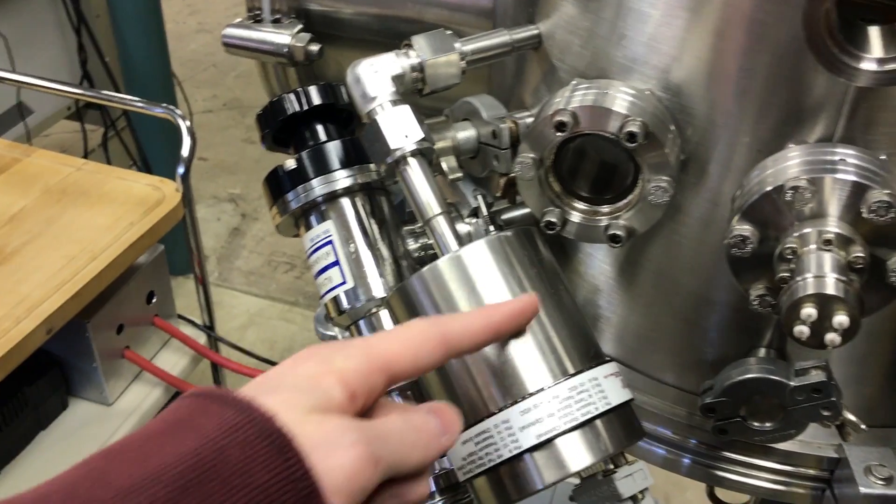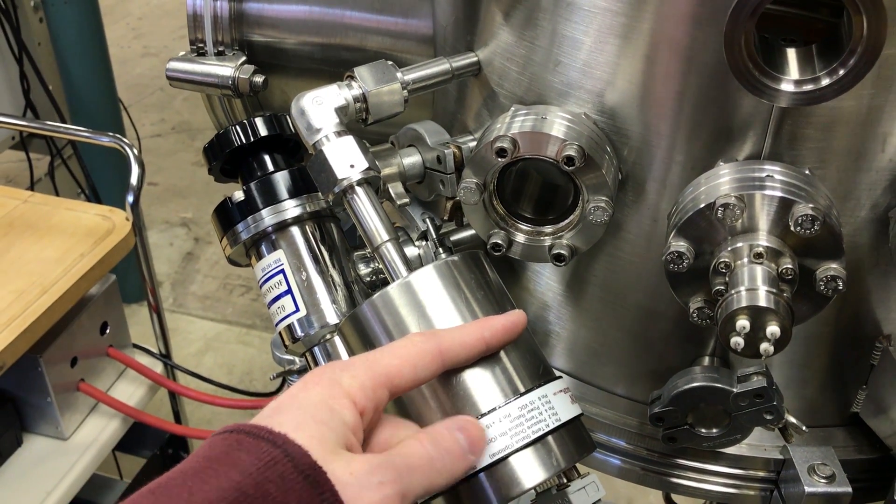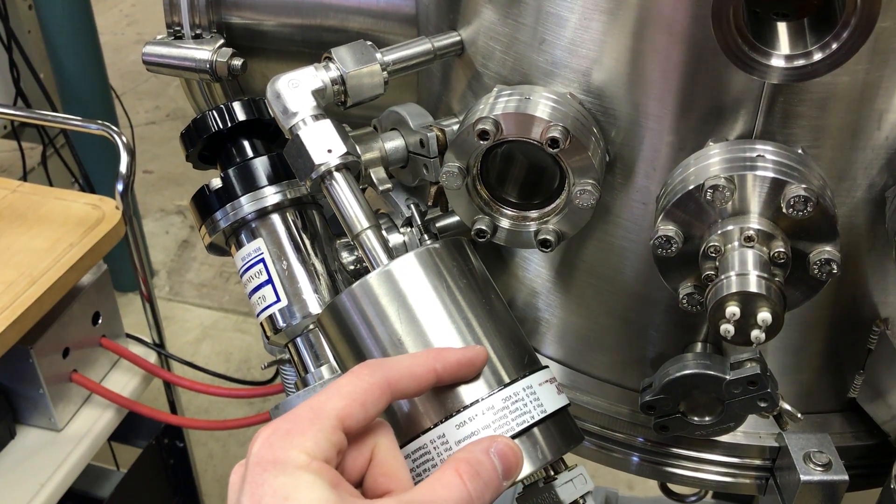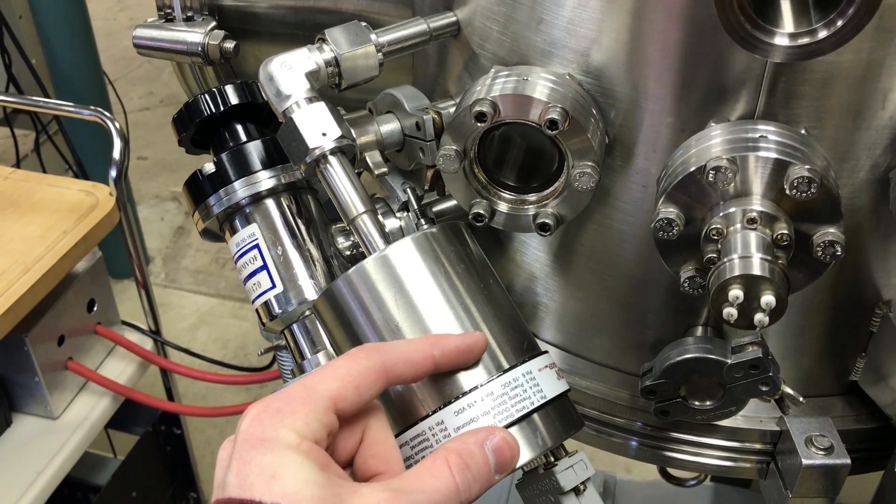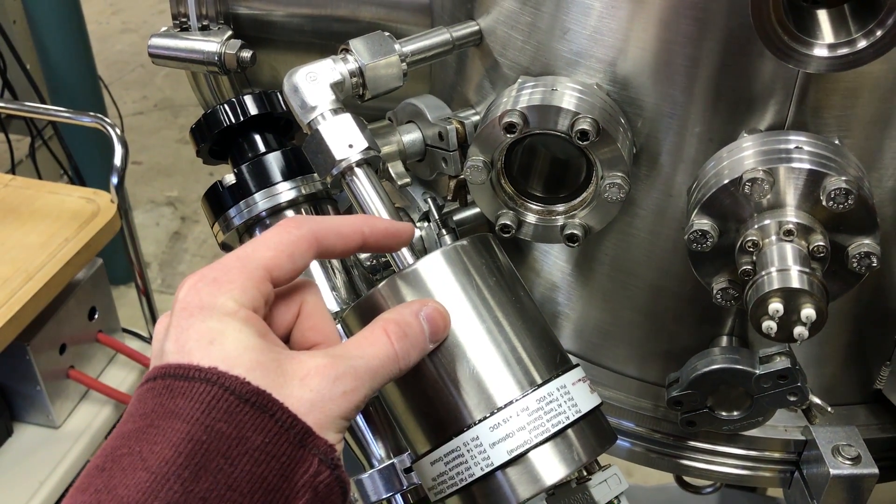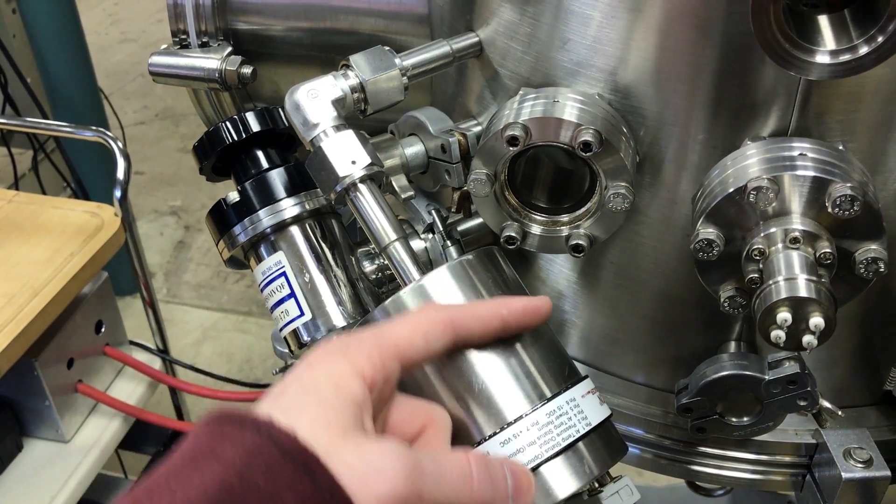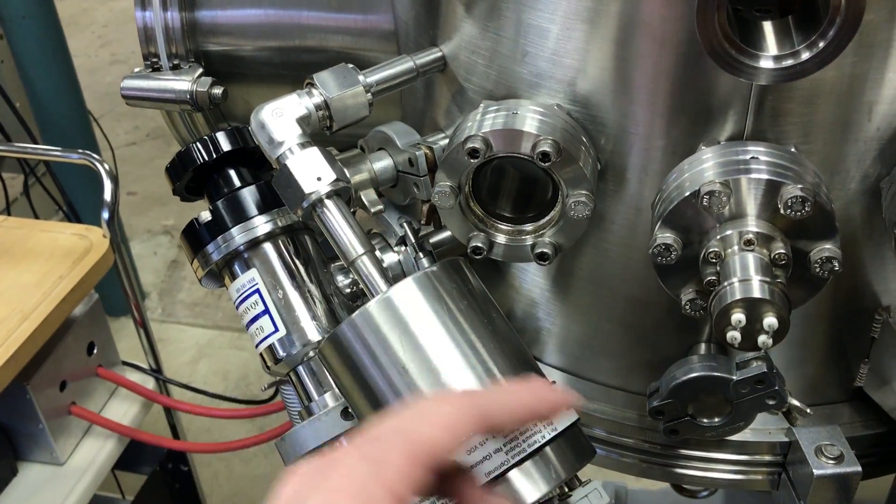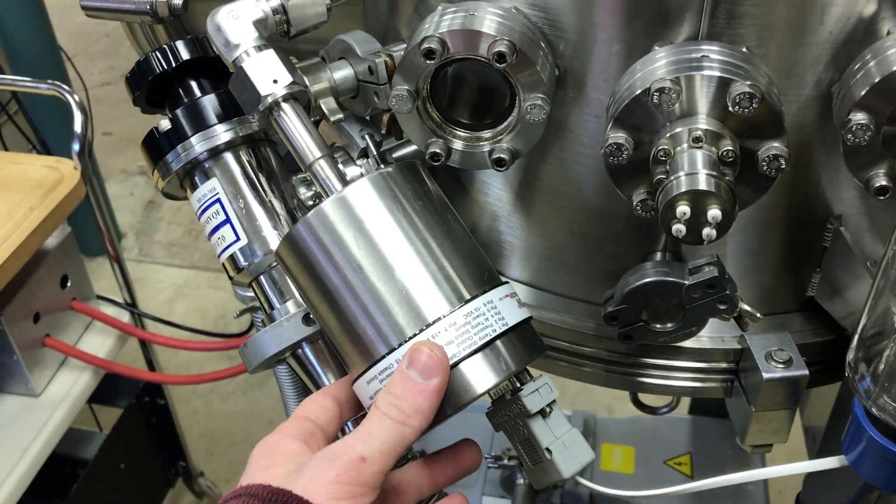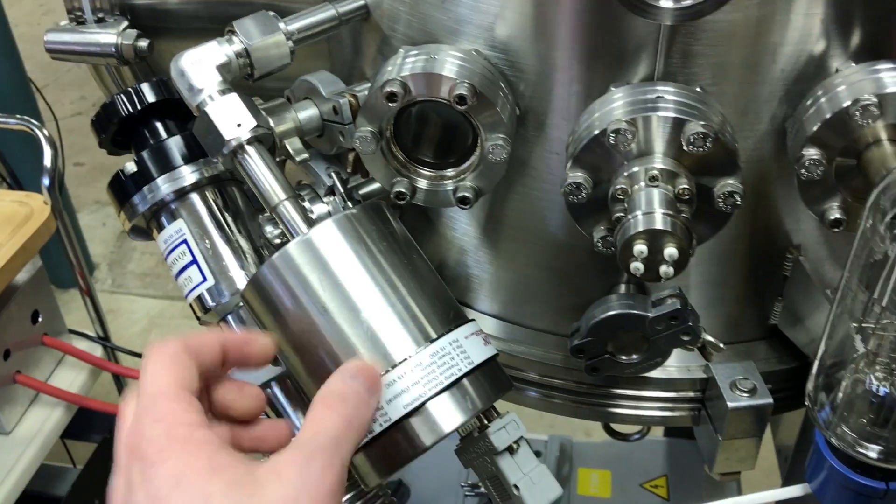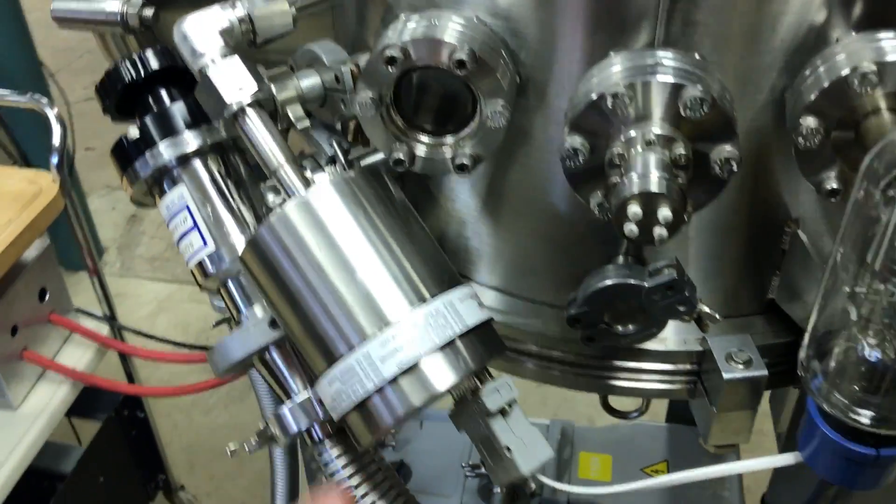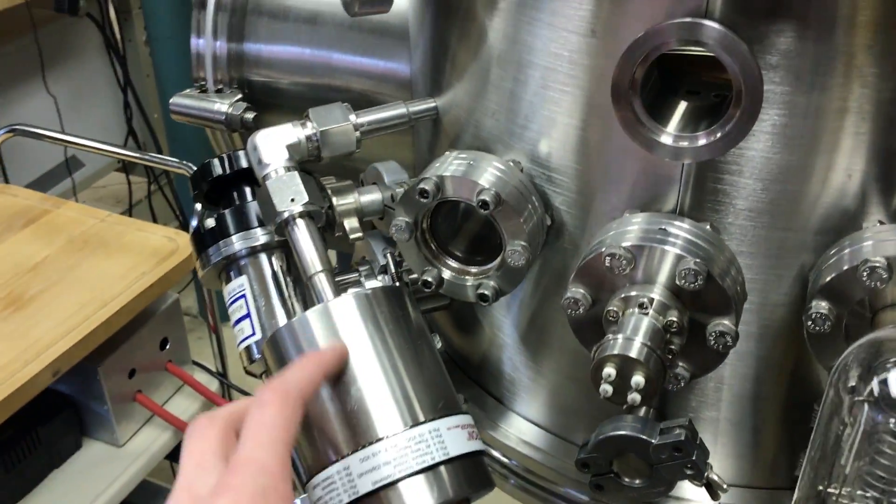This has basically got a diaphragm in the middle of it, and it's got a known vacuum on this side of it that's chemically gettered, and then it's got your vacuum chamber on this side, and then the disc will deform either way, and you can measure the capacitance change, and then therefore you can get your absolute pressure if you know the vacuum that's inside of this.